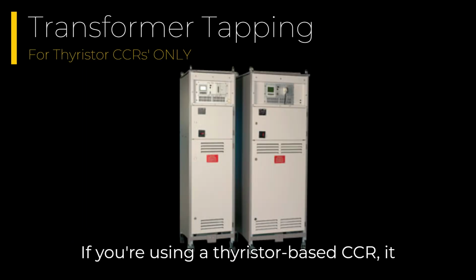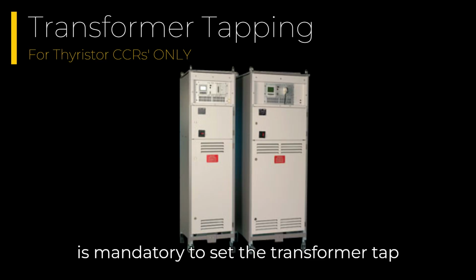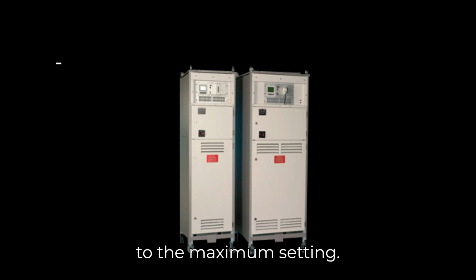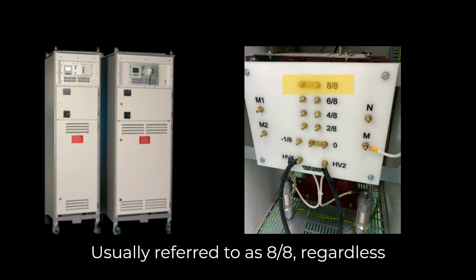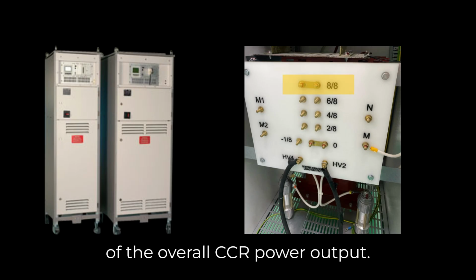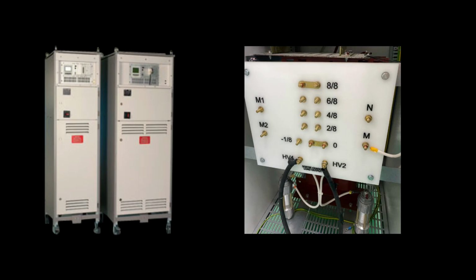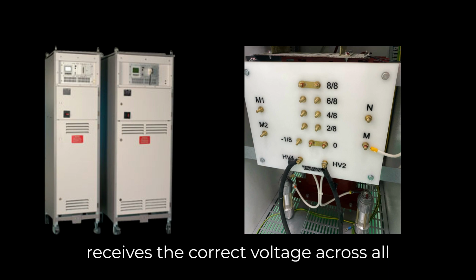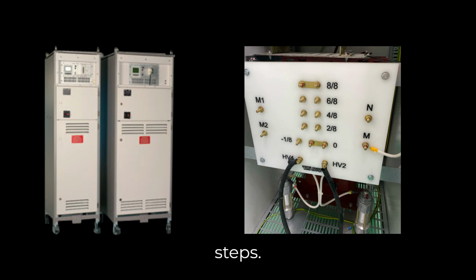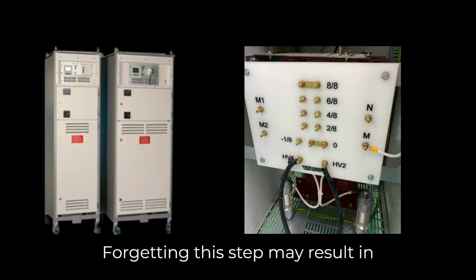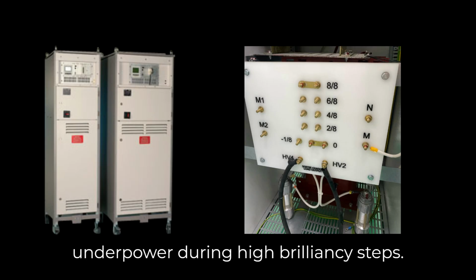If you're using a thyristor-based CCR, it is mandatory to set the transformer tap to the maximum setting, usually referred to as 8/8, regardless of the overall CCR power output. This ensures that the PAPI system receives the correct voltage across all steps. Forgetting this step may result in underpower during high brilliancy steps.